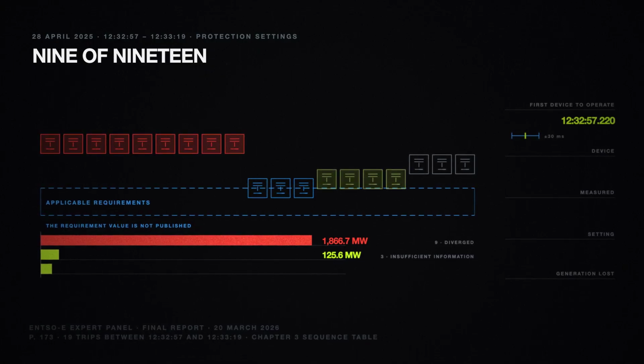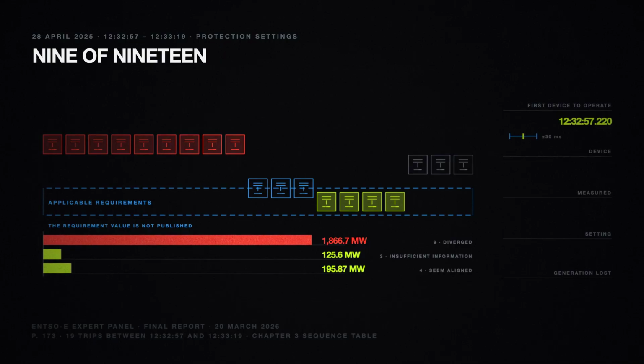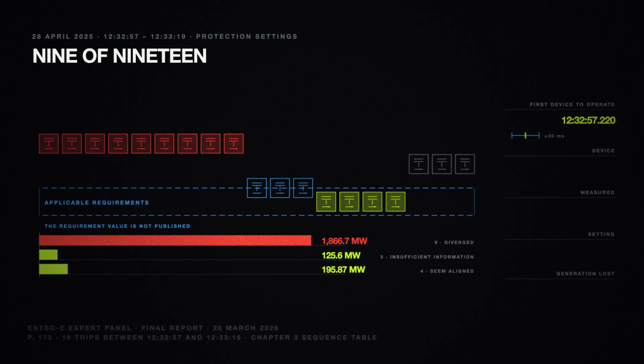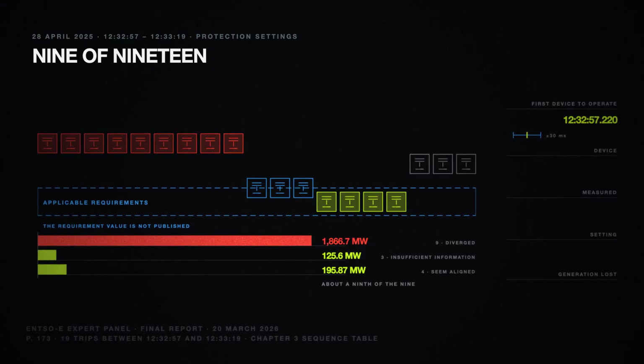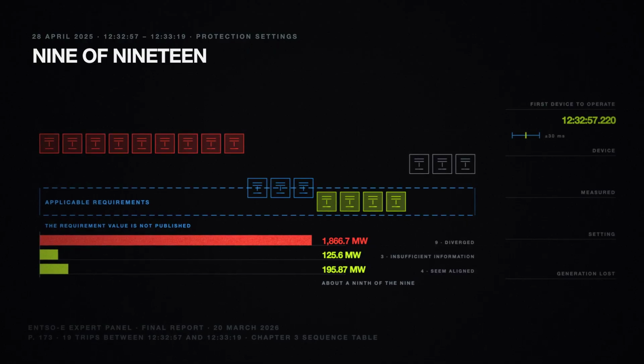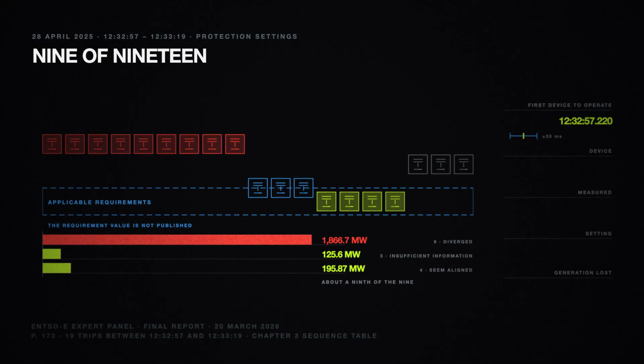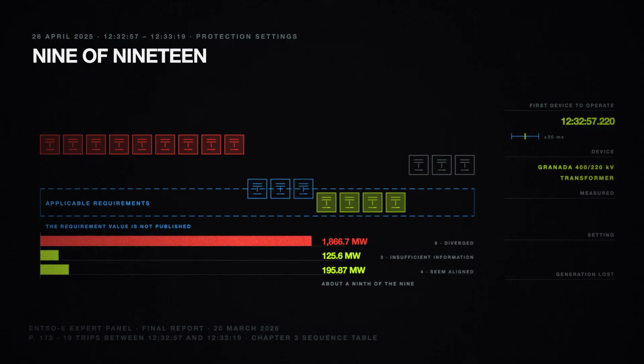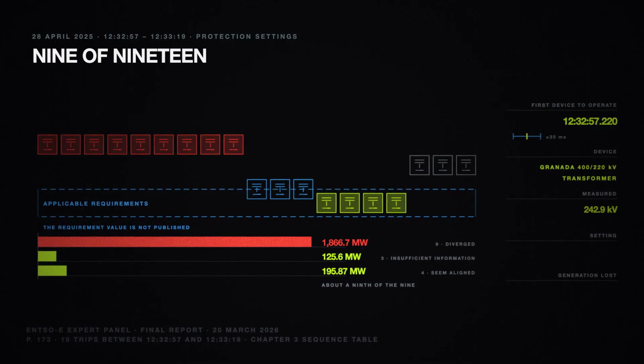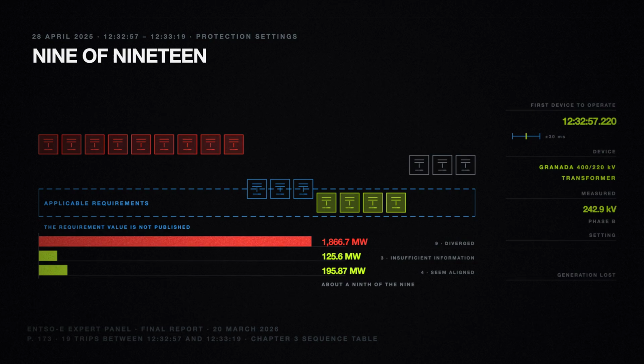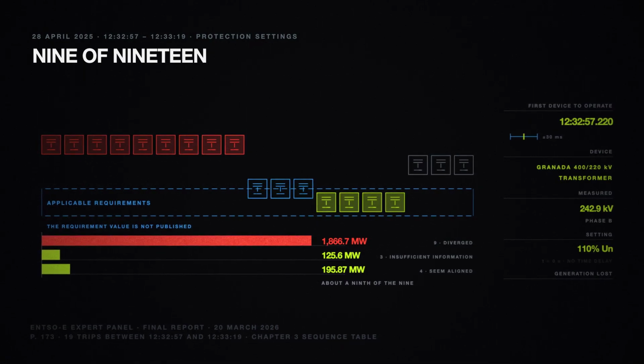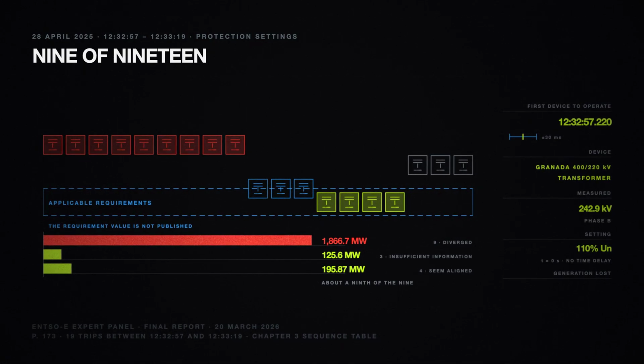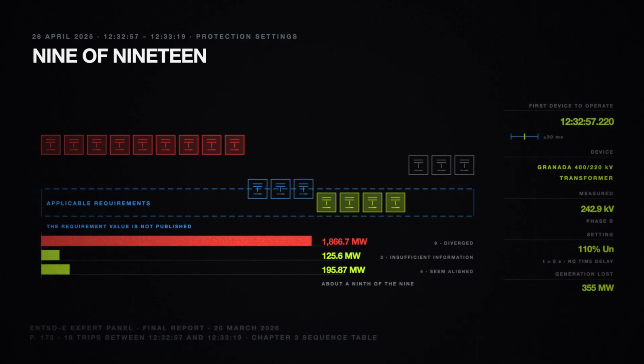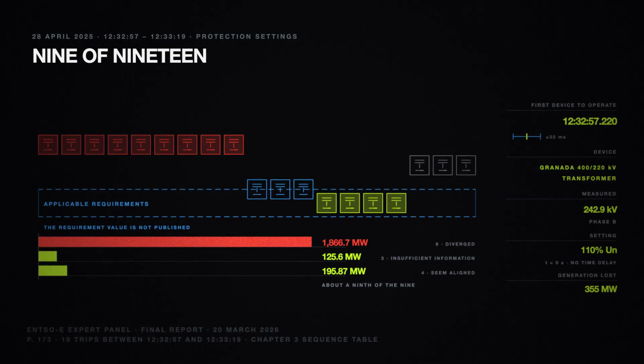Only 4 of the trips, 195.87 megawatts, seem aligned with the applicable requirements. 4 devices that appear to have done what was asked of them, and between them they took off about 1/9 of what the 9 took. 1 device in the 19 is described completely, and it is the first one. The transformer at Granada, 242.9 kilovolts on phase B, a setting of 110% of nominal, no time delay, 355 megawatts.